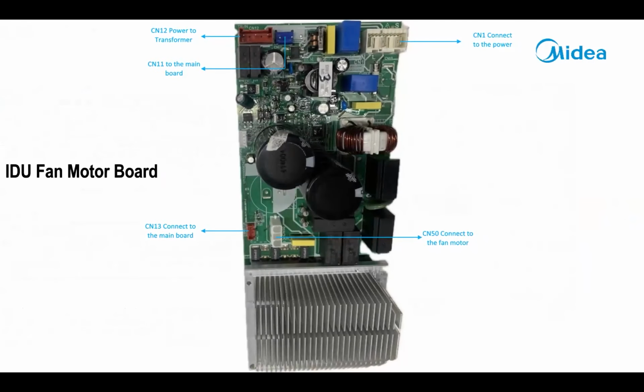Indoor fan motor board. This is your fan drive. That is a true DC motor, so it will ohm out like a 3-phase motor. CN1 is your power input. That comes from your L1, L2 from your power. That's where your power plugs into the board.